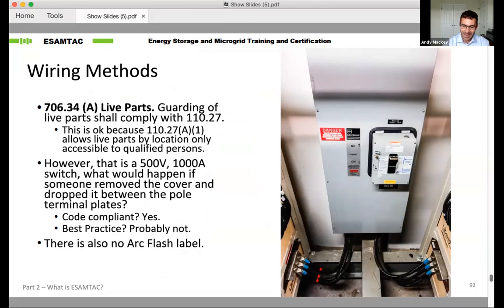Here's another example. I hate to do the scared straight approach, but sometimes it's interesting to see. This piece of equipment is a switch for a battery storage system in a data center, and the two shiny metal bar parts at the bottom are the most negative and most positive points of the array. If somebody took that cover off and dropped it between those connection points, they'd have a really bad day. This operates at over 500 volts with multiple thousands of amps available, with no fuses or circuit breakers between them. It would simply keep burning and arcing until there was a catastrophic failure where the metal melted away. Just an example of the nuances of risks that not everybody sees unless they've had the experience.